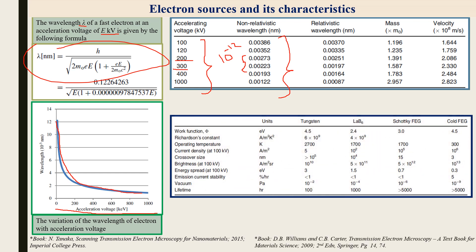The slide shows the difference between thermionic emission and field emission sources. For thermionic emission, tungsten and lanthanum hexaboride guns are used. Older TEM systems use tungsten guns, and newer TEMs mostly use lanthanum hexaboride. Advanced TEM systems with STEM capabilities and monochromators use Schottky FEG and cold FEG sources.